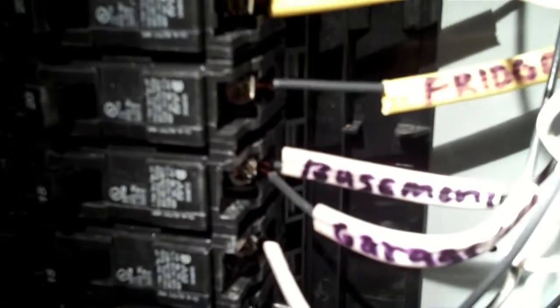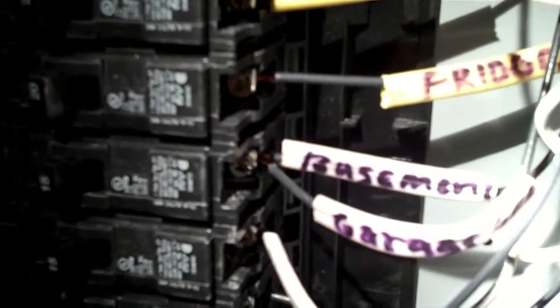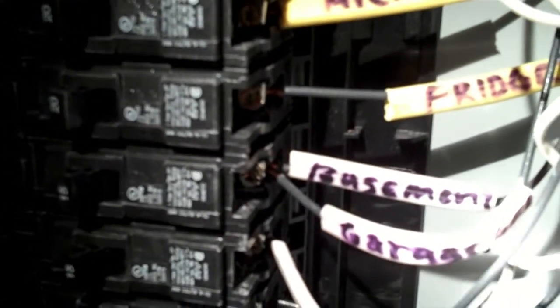Another strange thing with this new construction electrical install is that there is a double tap circuit breaker. If you can see right there, there's two wires going into one circuit breaker, which is definitely not code and actually considered a fire hazard.